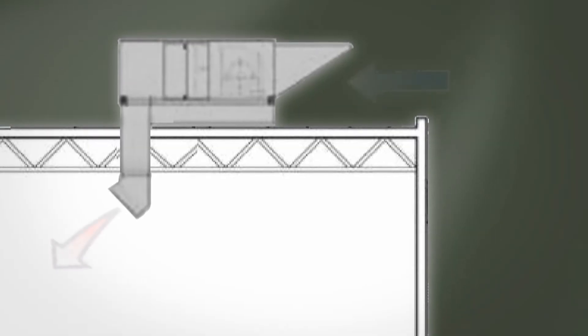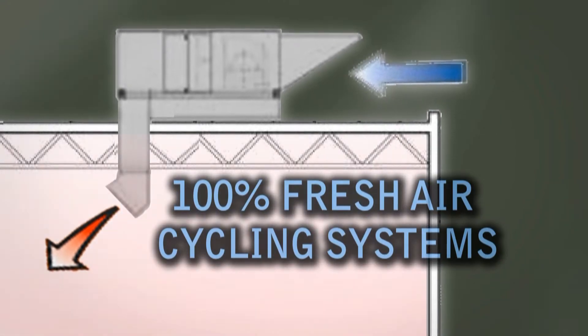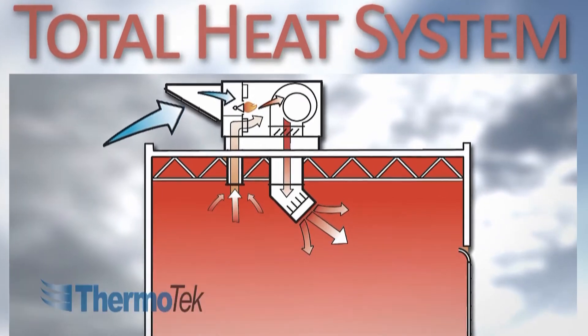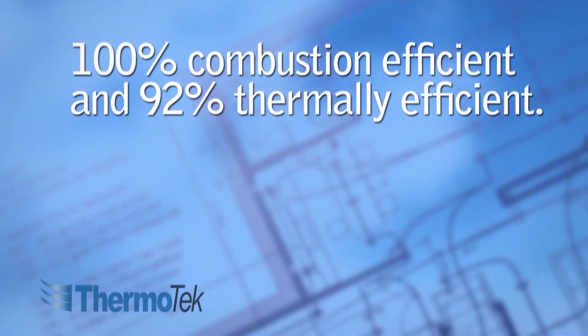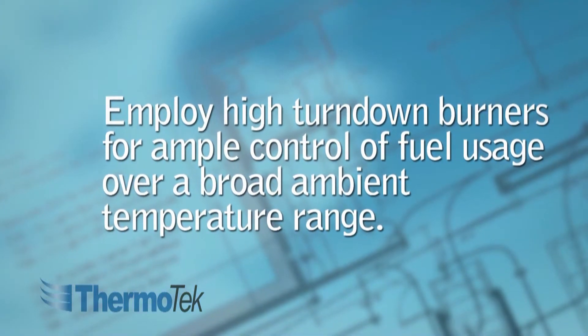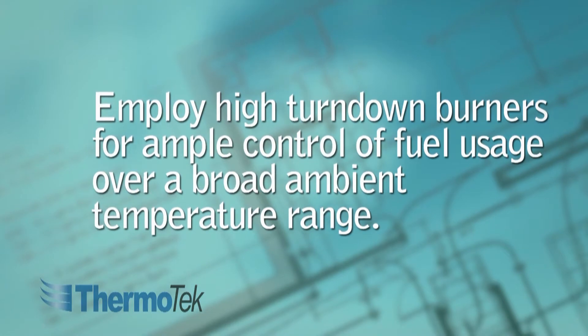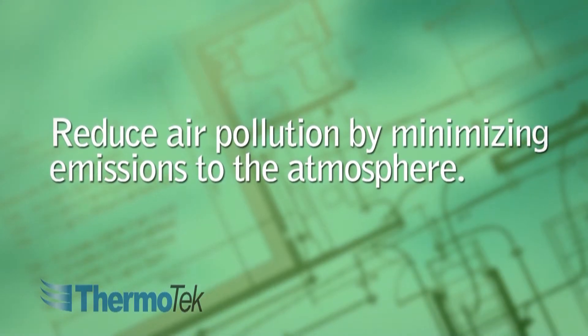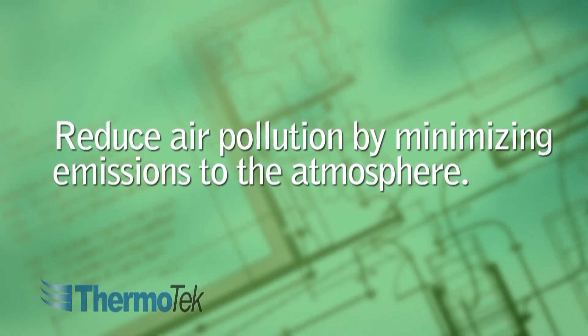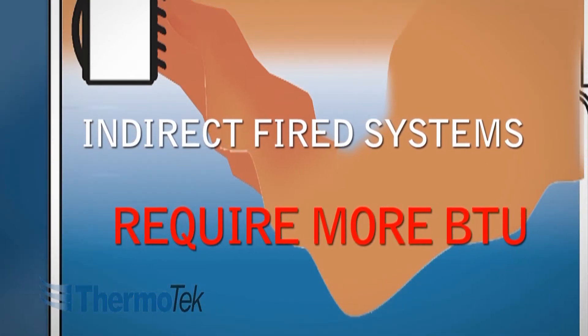Let's take a closer look at the two prominent systems currently used to heat large open space facilities: the 100% fresh air high temperature cycling system, and the recirculating system with pressurization, or the total heat system. Both systems are 100% combustion efficient and 92% thermally efficient. Both systems employ high turndown burners for ample control of fuel usage over a broad ambient temperature range, and both systems help to reduce air pollution by minimizing emissions to the atmosphere versus indirect fired systems that require more BTU for the same amount of heating.